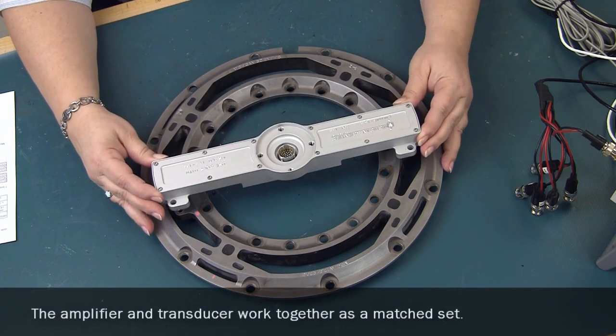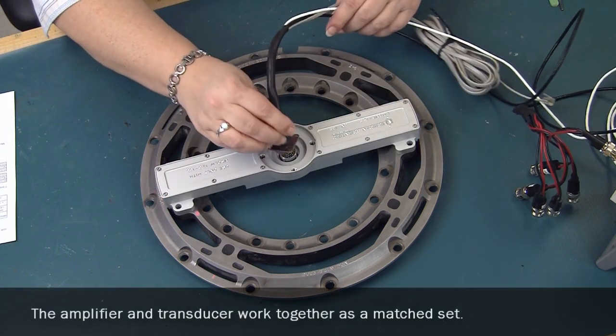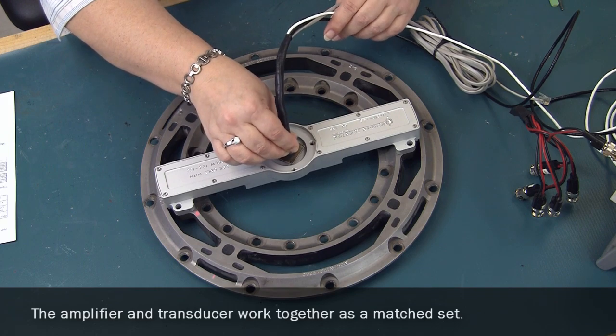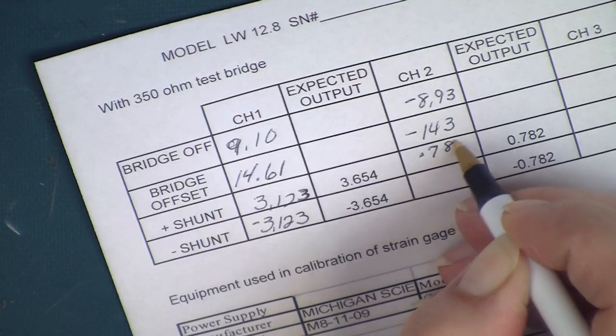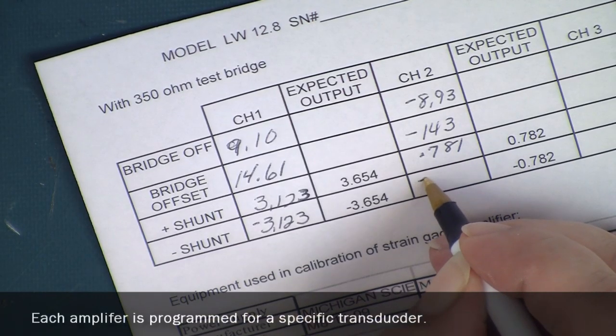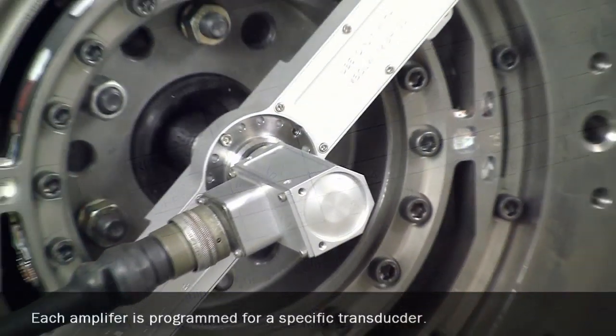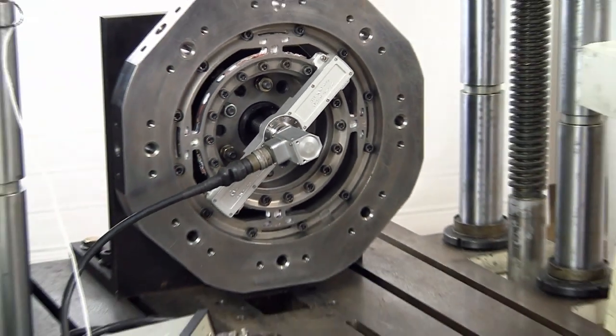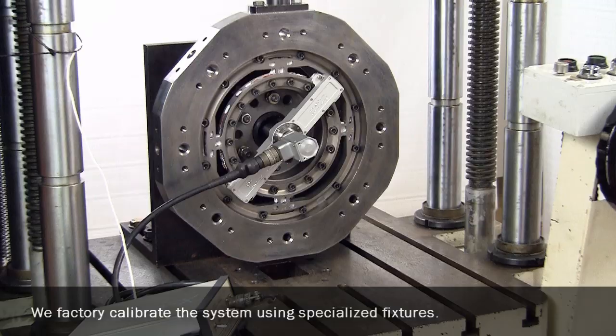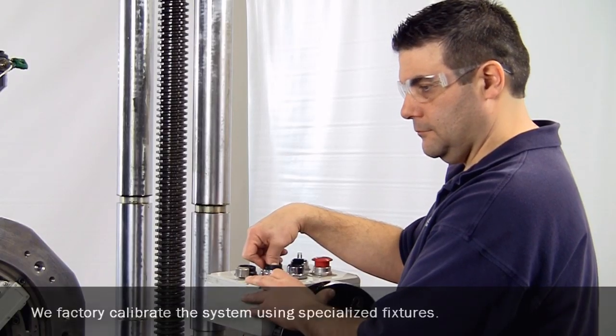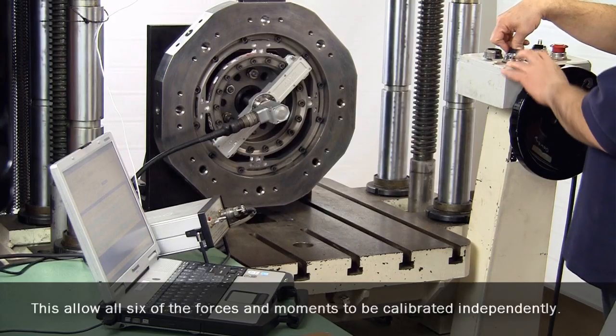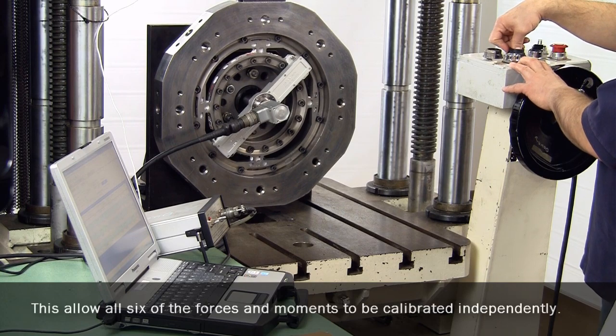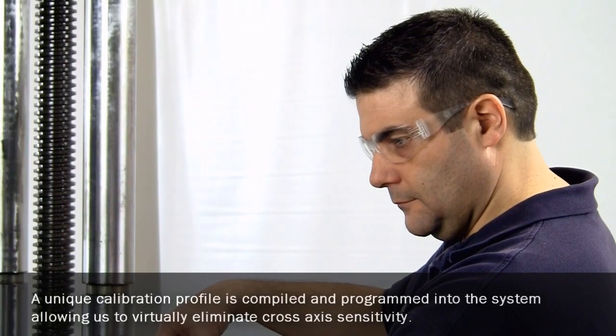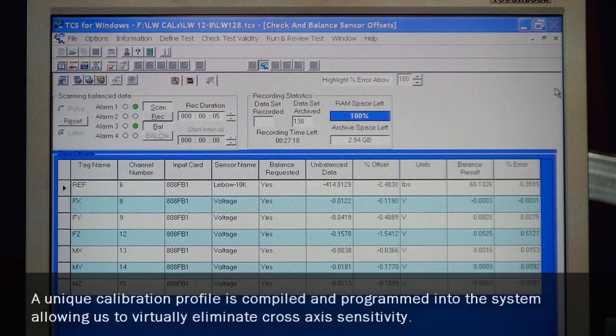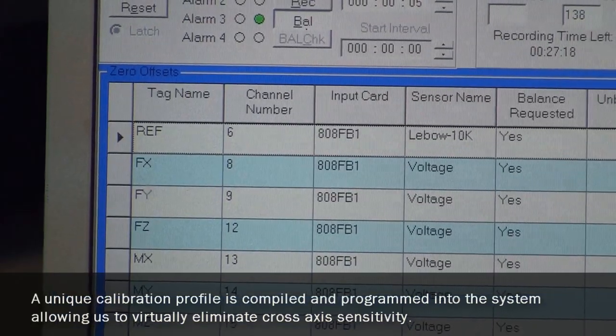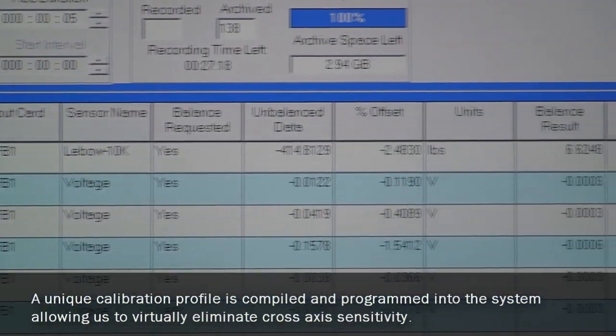The amplifier and transducer work together as a matched set. Each amplifier is programmed for a specific transducer. We factory calibrate the system using specialized fixtures. This allows all 6 forces and moments to be calculated independently. A unique calibration profile is compiled and programmed into the system, allowing us to virtually eliminate cross-axis sensitivity.